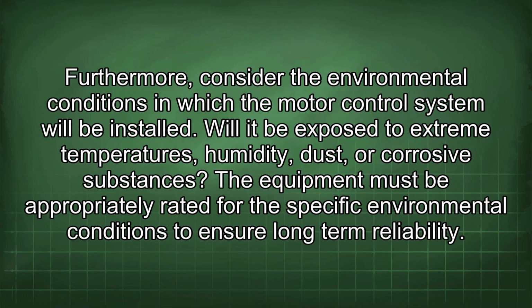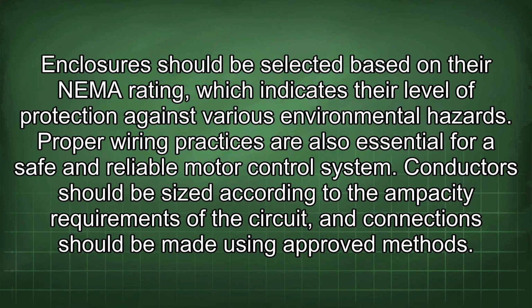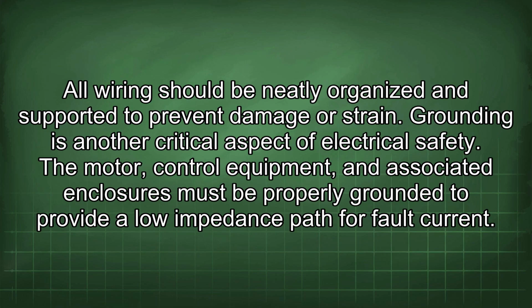Furthermore, consider the environmental conditions in which the motor control system will be installed. Will it be exposed to extreme temperatures, humidity, dust, or corrosive substances? The equipment must be appropriately rated for the specific environmental conditions to ensure long-term reliability. Enclosures should be selected based on the NEMA rating, which indicates their level of protection against various environmental hazards. Proper wiring practices are also essential for a safe and reliable motor control system. Conductors should be sized according to the ampacity requirements of the circuit, and connections should be made using approved methods. All wiring should be neatly organized and supported to prevent damage or strain.